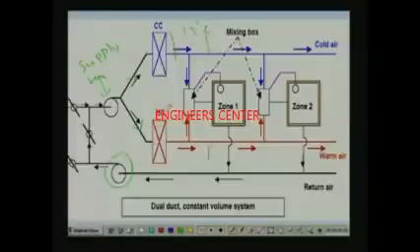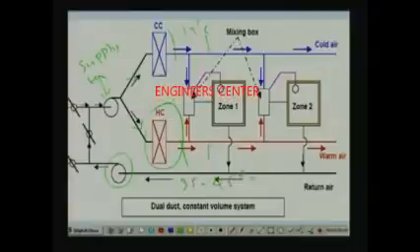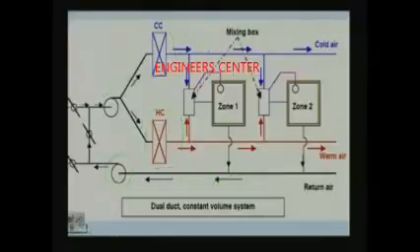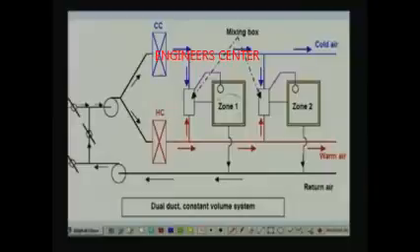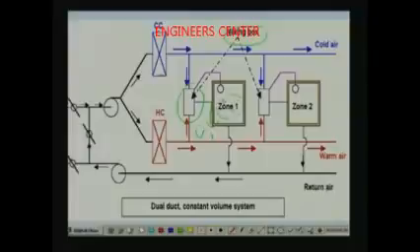Whereas in duct 2, you have a heating coil — HC stands for heating coil. So the air flowing through duct 2 is heated to about 35 to 45 degrees centigrade. So in one duct you have hot air at about 45 degrees centigrade, and in another duct you have cold air at about 13 degrees centigrade. These hot and cold air streams are mixed before each zone — for example, zone 1 — depending upon its load, in what is known as a mixing box.